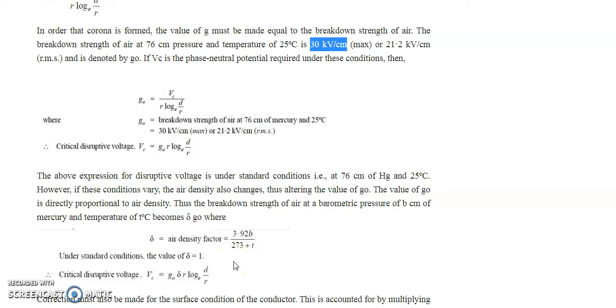The above expression for disruptive voltage is under the standard condition. However, if these conditions vary, the air density also changes, thus altering the value of g naught. The g naught is nothing but the critical breakdown strength of the air. The value of g naught is directly proportional to the air density, and your density of air is equal to the density factor delta. These are the already derived mathematical expressions, you don't worry about this.